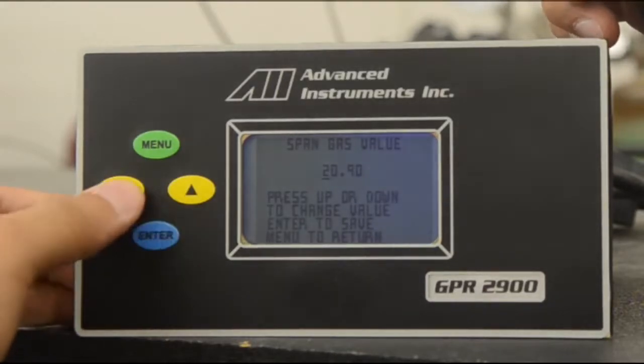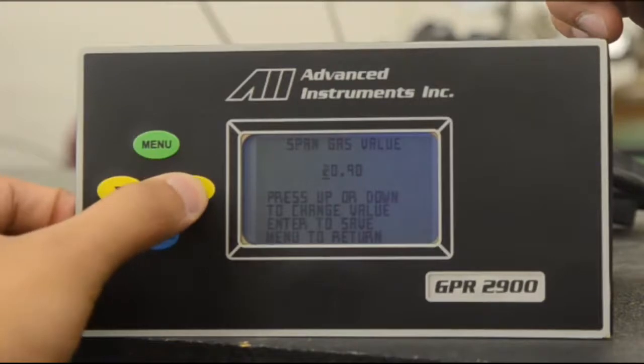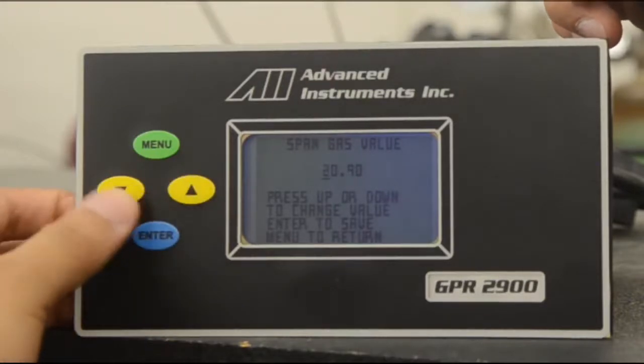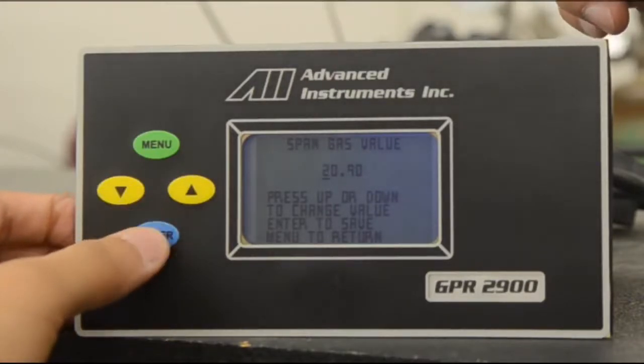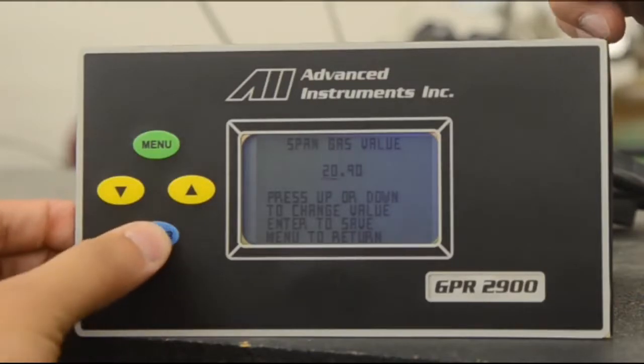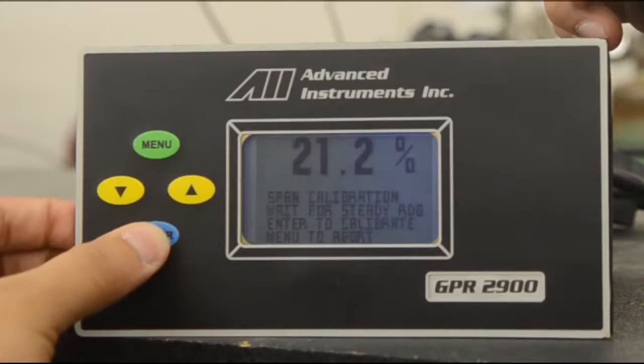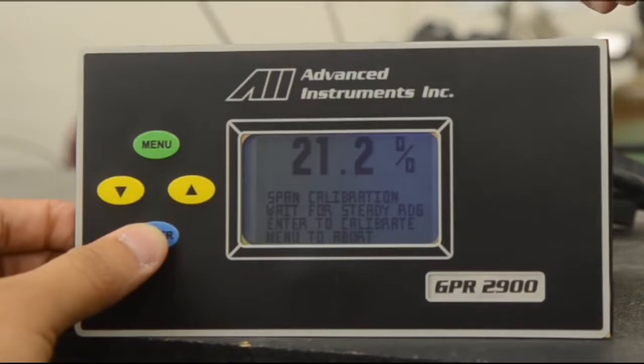If you would like to change that, you can hit the up or down buttons to change the value. However, for this air calibration, 20.9 will do. You press enter to scroll through each digit, and once you are complete, you'll get taken to a menu that looks like the home screen. This is done to show you the actual live output of the sensor reading in the air, and it will give you two options. 1, hit enter to calibrate, or 2, menu to abort.